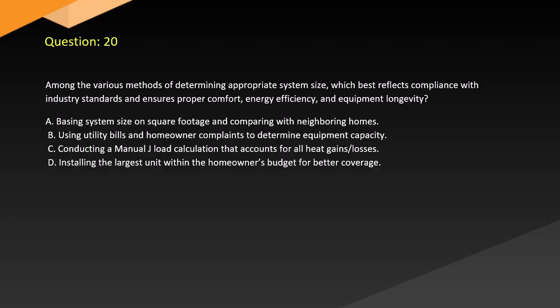Question 20. Among the various methods of determining appropriate system size, which best reflects compliance with industry standards and ensures proper comfort, energy efficiency, and equipment longevity? A. Basing system size on square footage and comparing with neighboring homes. B. Using utility bills and homeowner complaints to determine equipment capacity. C. Conducting a Manual J load calculation that accounts for all heat gains and losses. D. Installing the largest unit within the homeowner's budget for better coverage.